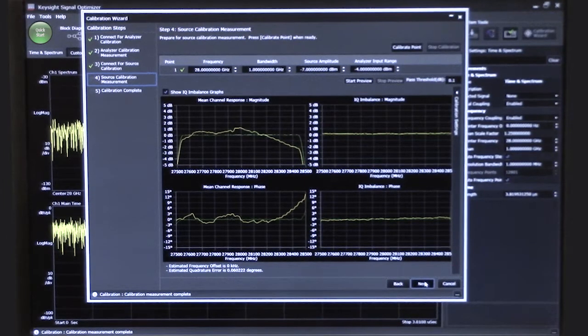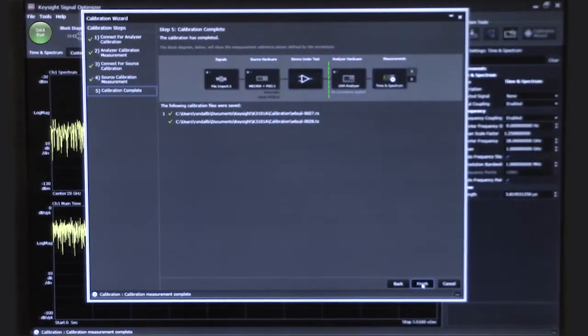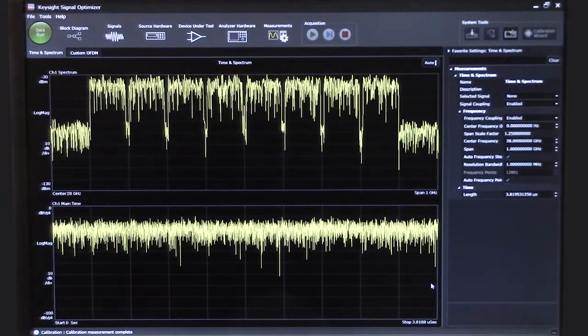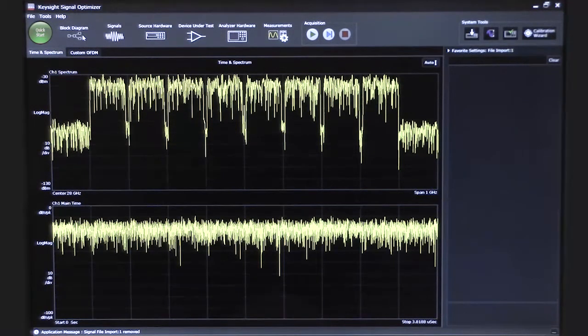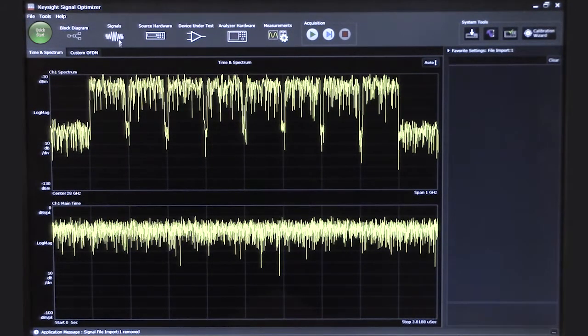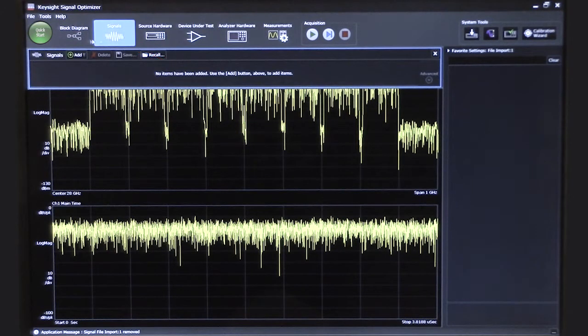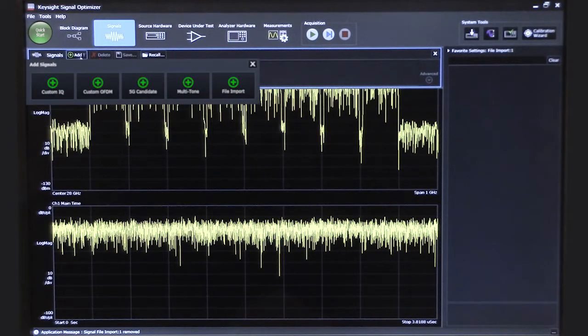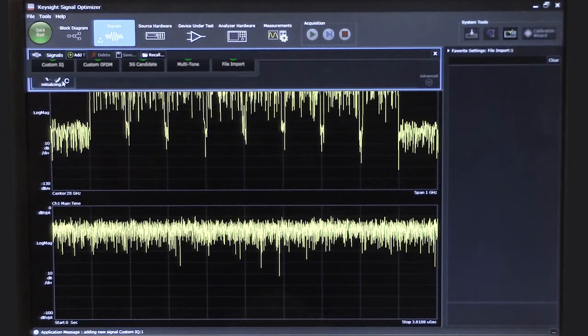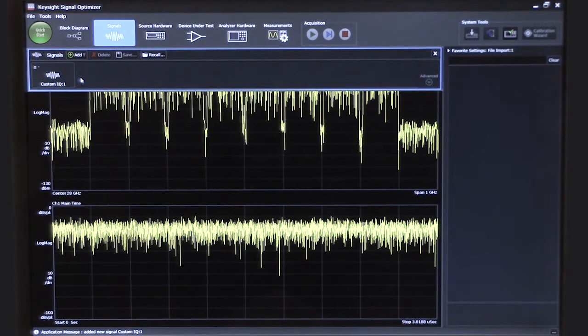We're satisfied with our results, so we can say next and finish the calibration. Now that we've calibrated the system, let's use the software to generate a signal and then analyze it. We'll do this for two types of signals — the first one will be a simple single-carrier 16QAM signal, and then we'll do a pre-5G waveform. At the top of the screen we'll start with the signal block, and I can choose to add or delete various waveforms to my configuration. In this case I'm going to choose to do a custom IQ, and we're going to do a single-carrier waveform.